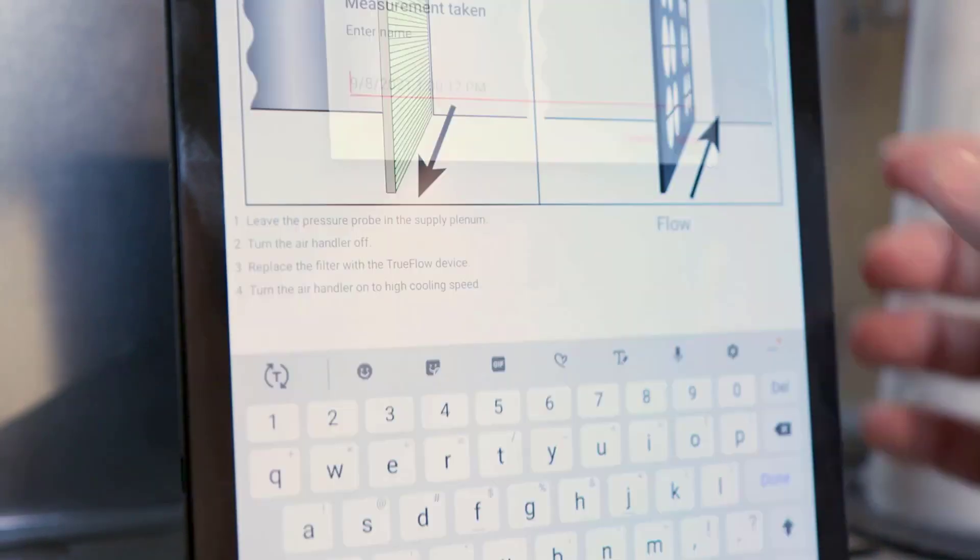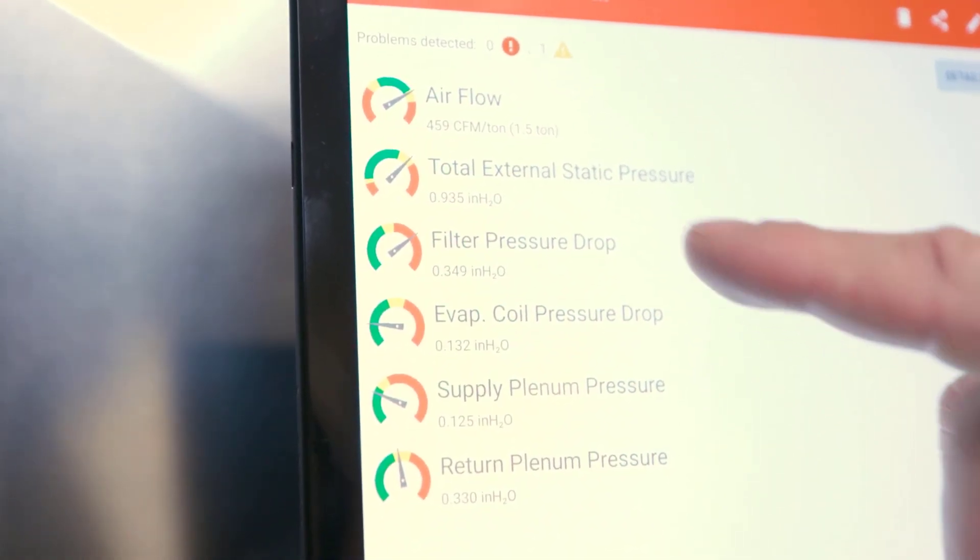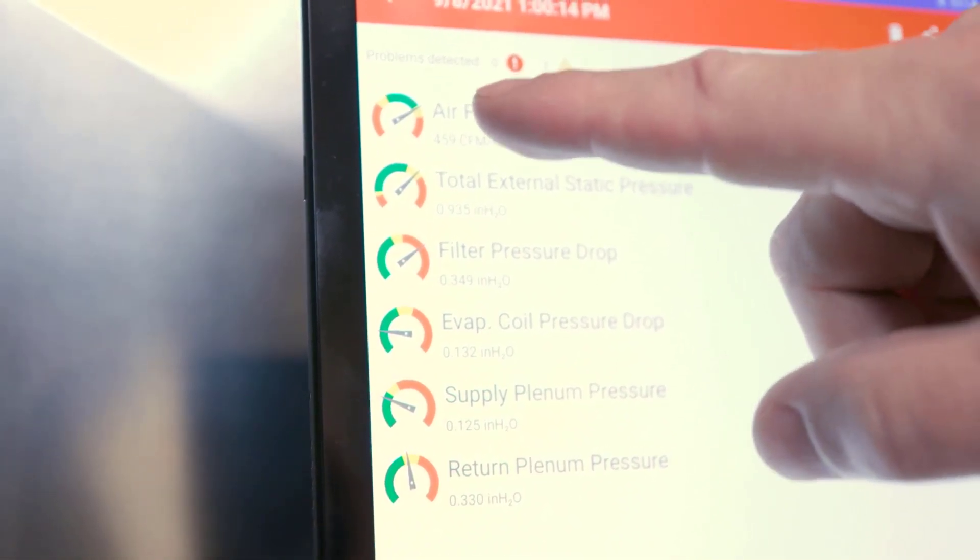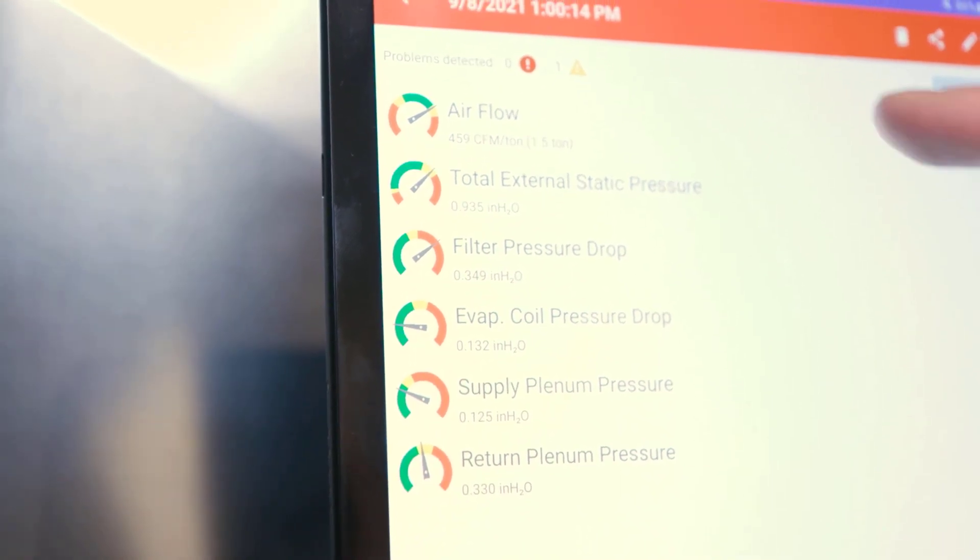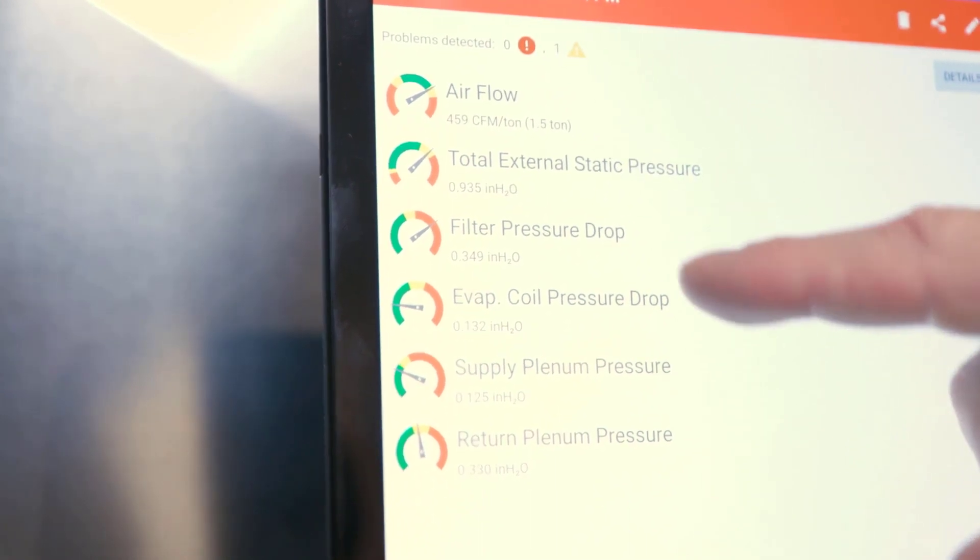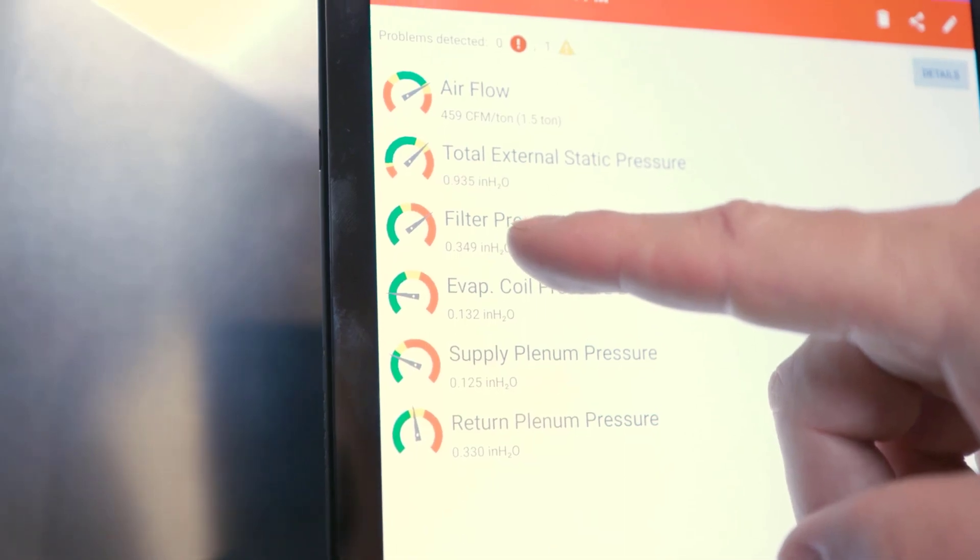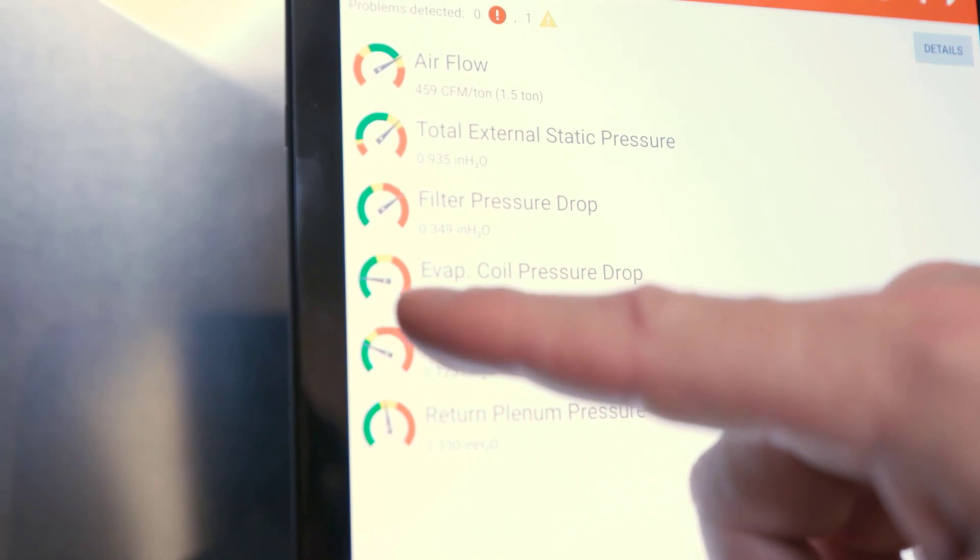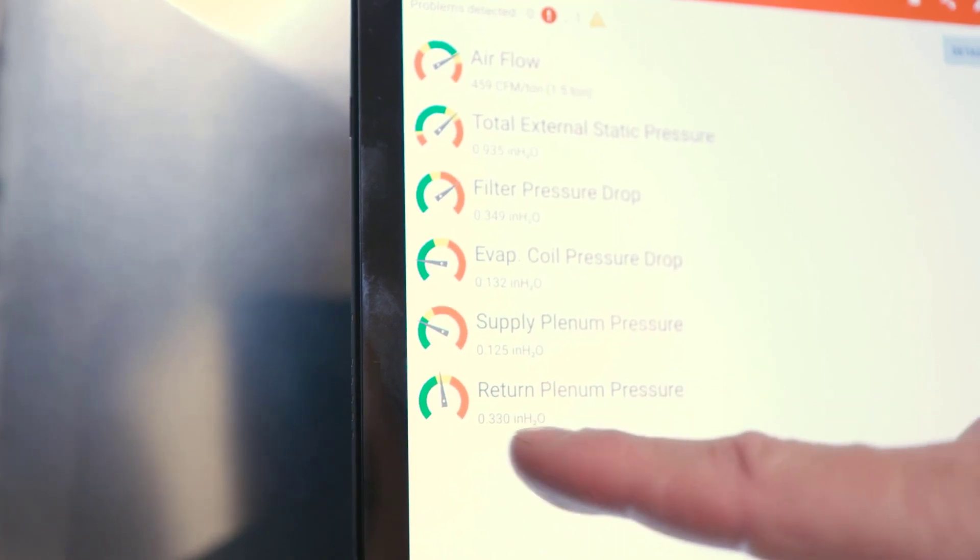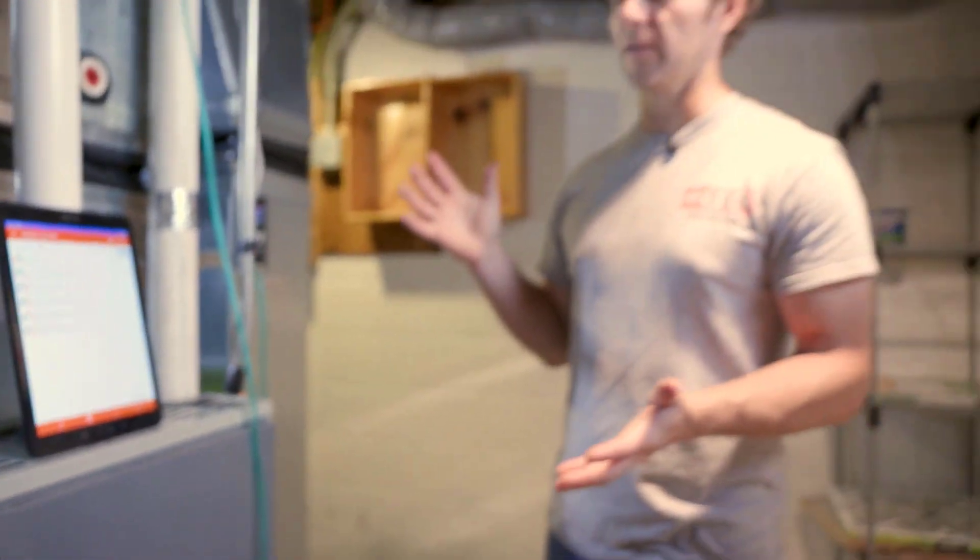We'll save that report and the results come up right away. A couple things jump out at me. We've got an airflow of 459 CFM per ton, so we're a little bit above the optimal range for total airflow. We have a high or kind of marginally high external static pressure at 0.935. Our filter drop pressure is in the red here, so this is really high. This is something that we'll take a look at. Our evaporator coil looks really good, it's in the green, so we don't see any problems with the pressure drop there. For our supply pressure it looks good, kind of on the edge there but in the green, and our return pressure is actually kind of in the yellow.